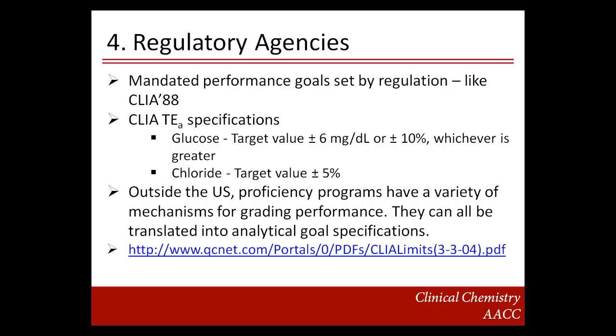The next in the hierarchy is quality specifications based on regulatory agencies. CLIA 88 specifications have a set of mandated performance goals. CLIA specifies the total allowable error for glucose as target value plus or minus 6 mg/dL, or target value plus or minus 10%, whichever is greater. For chloride, CLIA specifies target value plus or minus 5%. CLIA TEa limits tend to be wider than other TEa limits and are currently undergoing review, so they should always be the minimum.